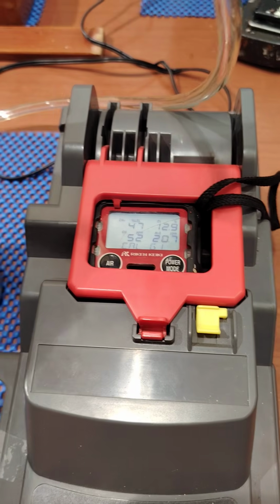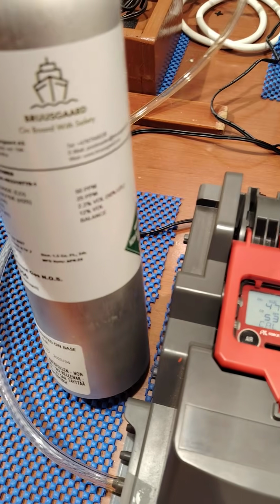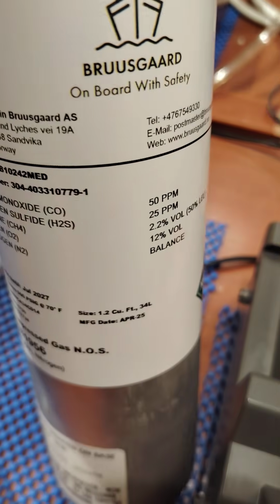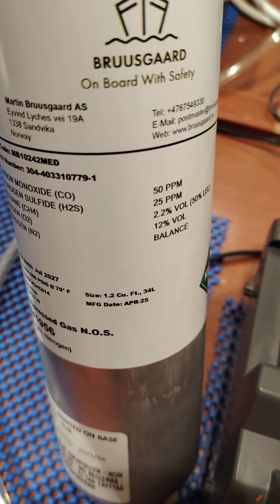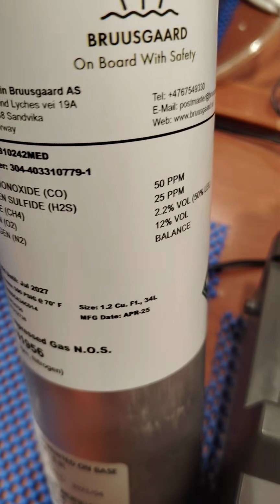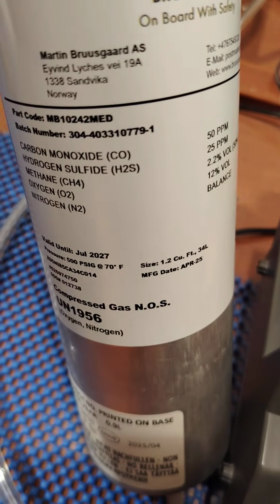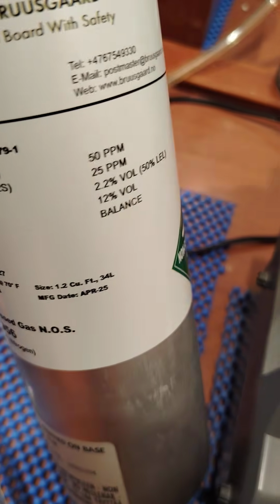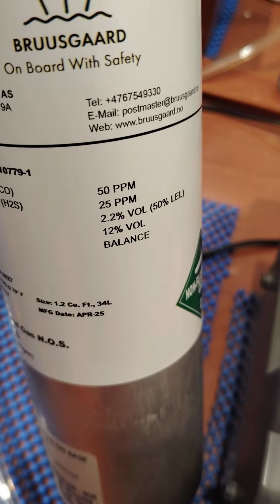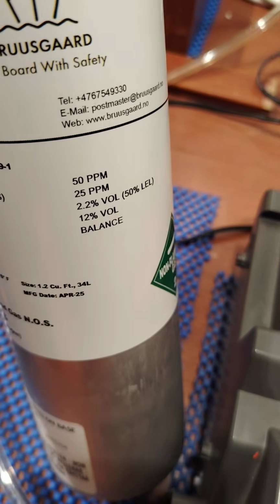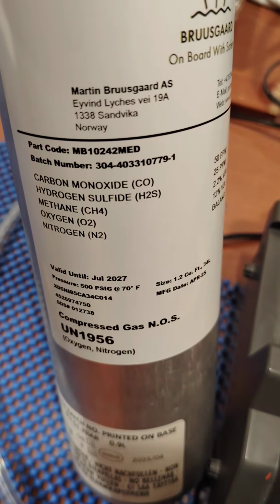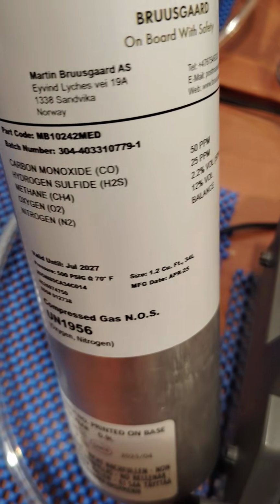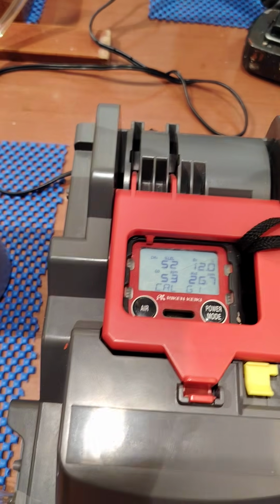So anyway, this is a multi gas detector. Okay, where the carbon monoxide is 50 ppm, hydrogen sulfide is 25, methane 2.2% by volume or equivalent to 50 LEL, and then remaining oxygen of 12% by volume, and nitrogen as the balance.